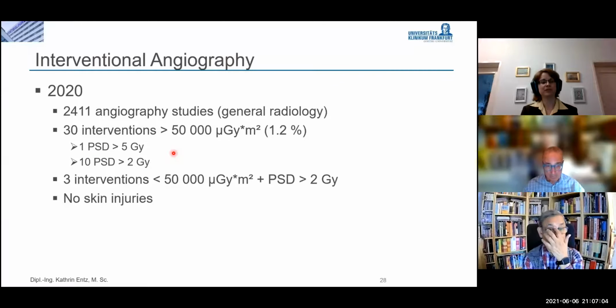And maybe you remember that 5 gray is the value where those skin injuries of grade 2 or higher can actually occur. So if you're staying below the level of 5 gray, you cannot actually have those because there are deterministic effects. So only one patient out of those 2,400 might have a skin injury. Then we had 10 where we exceeded the value of 2 grays, where you can find maybe mild injuries like little redness of the skin, but no severe injuries. But just in addition to those 30 interventions, we also had 3 interventions where the dose area product was below 50,000 micrograys times square meter. So actually below this reporting threshold, but we still had a peak skin dose of more than 2 gray.